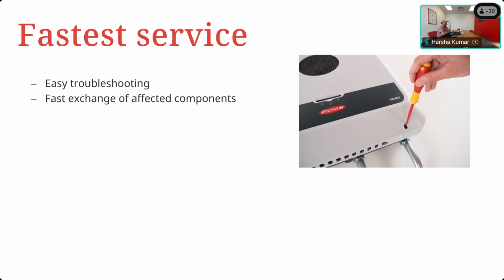In addition, we've kept the modular concept going. If you're trained as an FSP, just like you'd change out printed circuit boards instead of the full inverter on the older models, you can do the same here. Since you don't need to replace the full inverter, it's much quicker to replace printed circuit boards. Just like with the old Primos and Symos, if you need a replacement, we send you the power stage while the mounting bracket and wiring stay in place, since all of that is passive and doesn't need to be undone and redone. The same concept holds here as well.